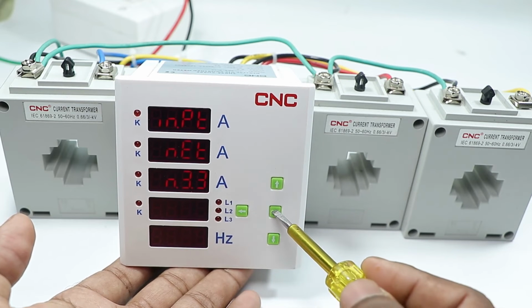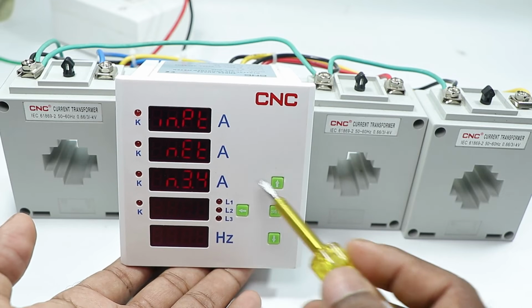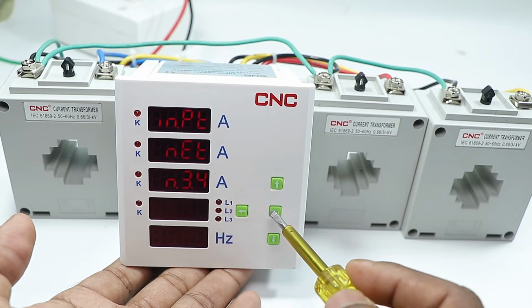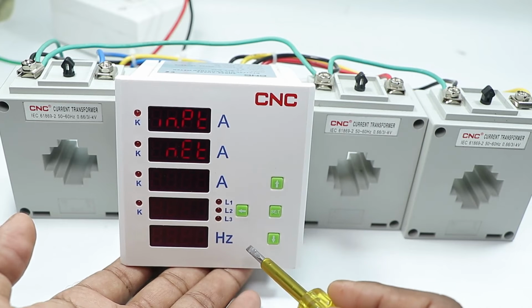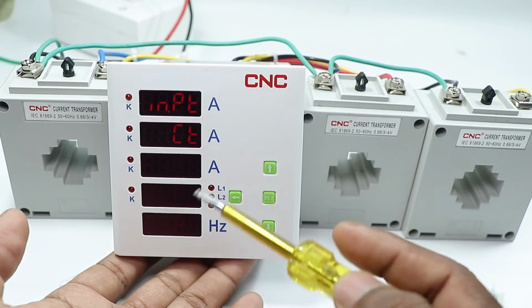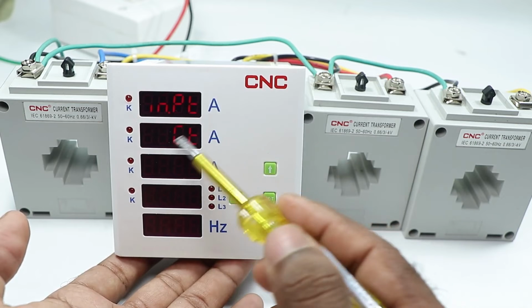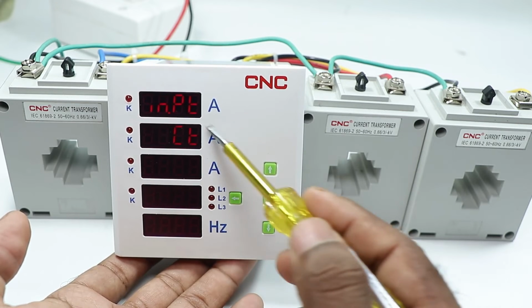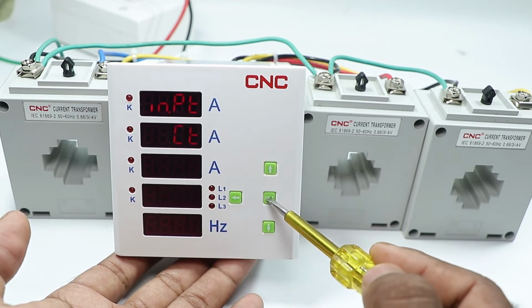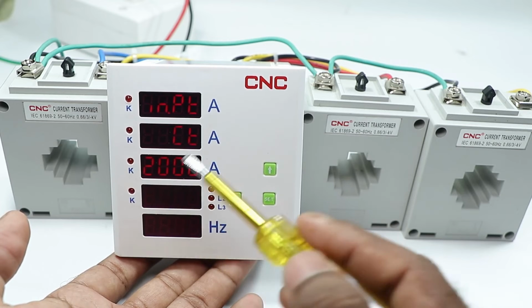Right now I have to program for 3 phase 4 wire because that's the connection I made. After this, I press the set button. When I press it, it shows CT, meaning the ratio of your CT has to be set here. So I press the set button, and you can see 2000 is the programming set.